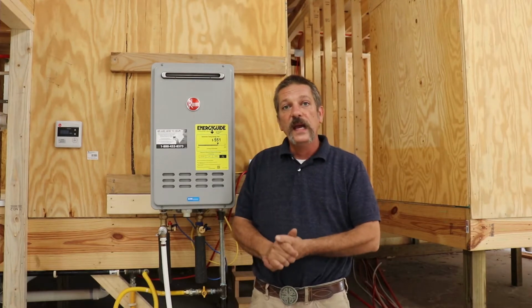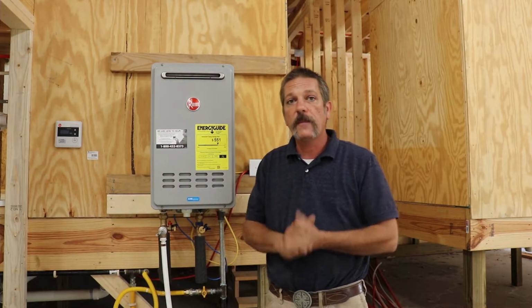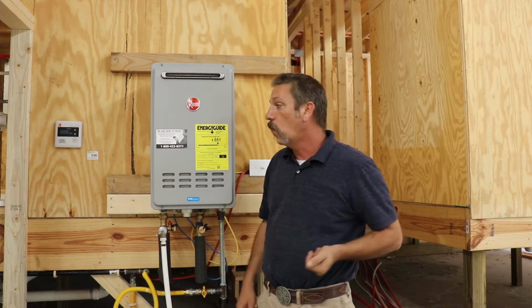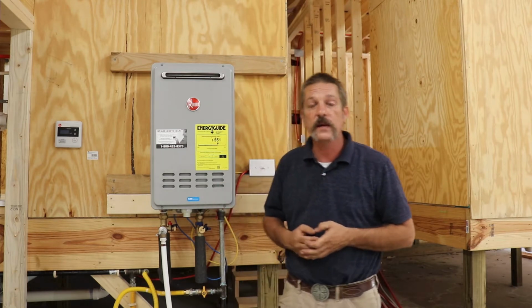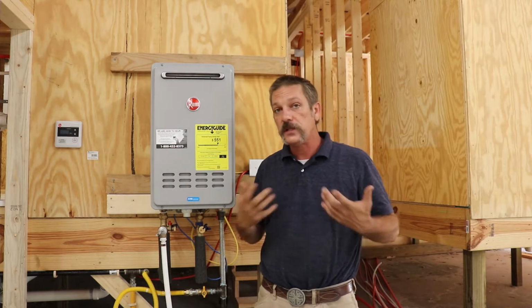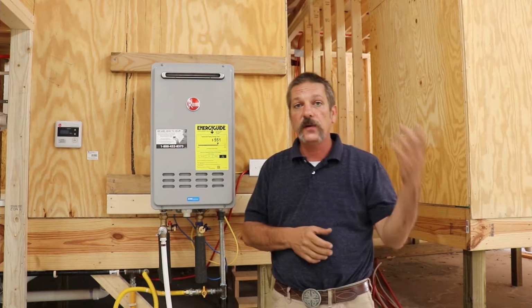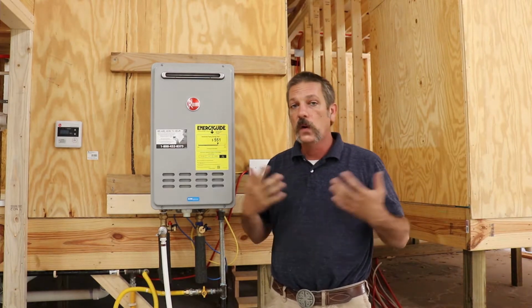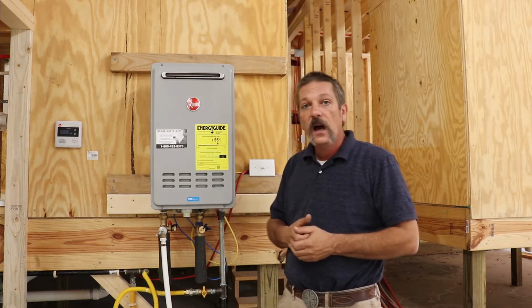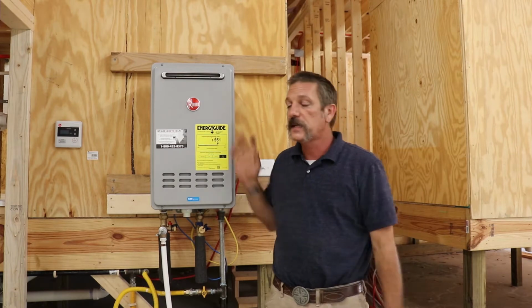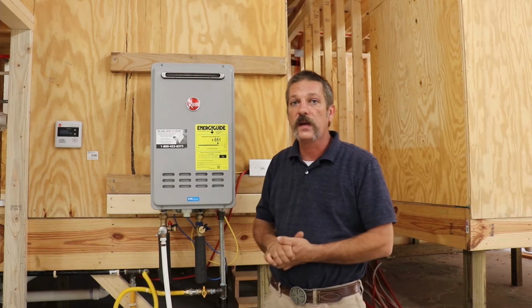In this episode, we're going to talk about how to flush out or descale a tankless water heater. This is something the manufacturer recommends you do annually, especially if you're in an area with hard water or calcium in it. You've got to clean out this heat exchanger, or that flow rate inside there is going to slow down and this thing will quit working.